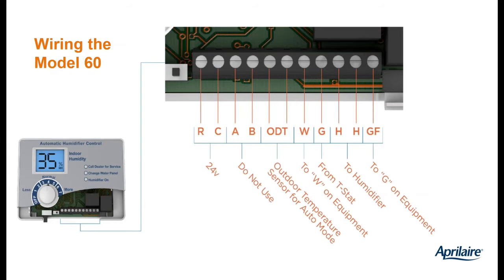The terminals inside are very straightforward. It's a very simple installation. We'll go through it, but you can see you've got your basic HVAC terminals, R, C, W, there's a couple G's in there that we'll talk about, a place to wire the outside temperature sensor, and then your HH terminals. That's how you're going to tell the humidifier to run. Obviously, that's pretty important. The AB terminals we're not even using. In fact, we're going to start offering humidistats in the near future that don't even contain those AB terminals.